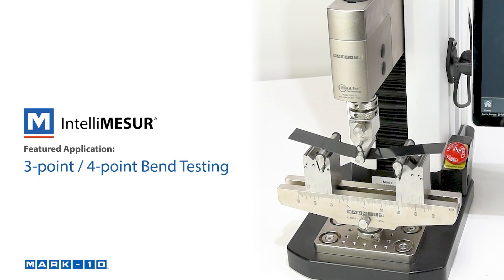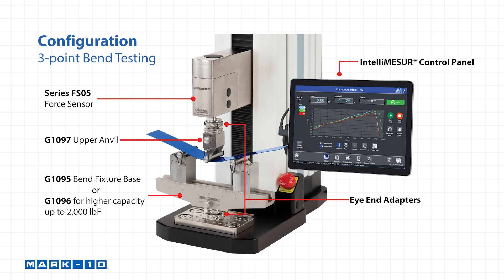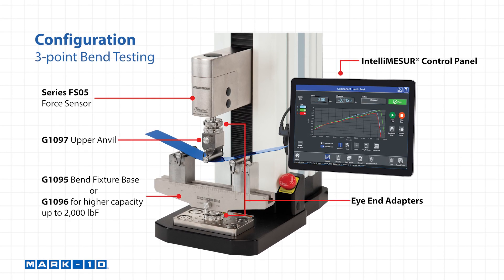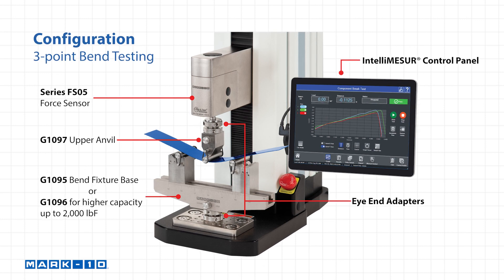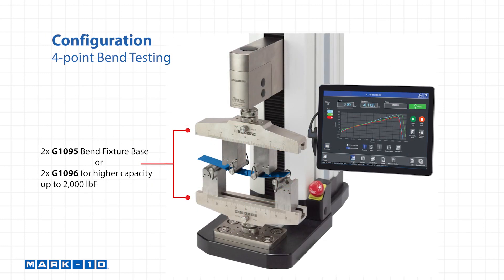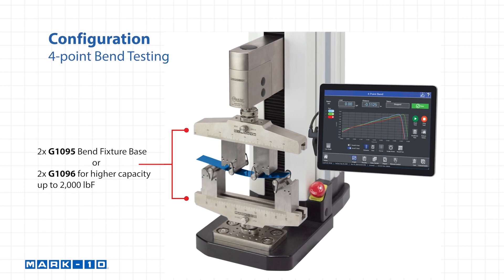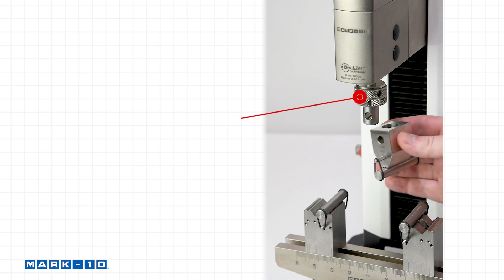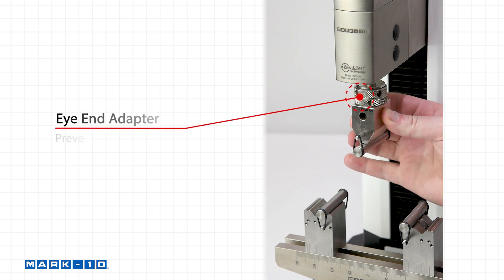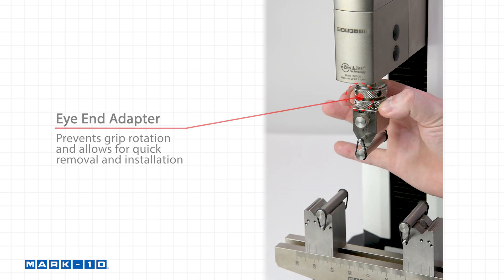Hello and welcome. This video features Mark 10's IntelliMESUR software. Let's take a look at the setup. We'll be doing some 3- and 4-point testing. Here's the configuration for 3-point bend testing, and also 4-point tests. You can see the G1097 Anvil is replaced with a second G1095 bend fixture base. Eye-end adapters prevent grip rotation and allow for quick removal and installation.